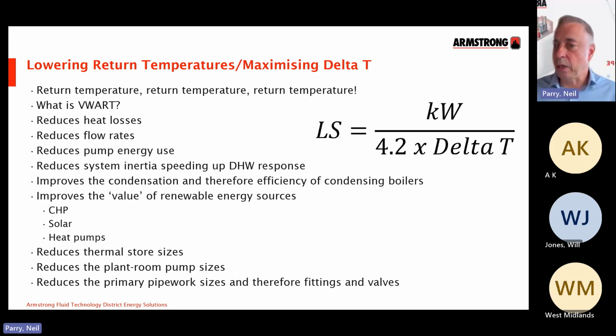We reduce heat losses from the network because you've effectively got one hot pipe and one much cooler pipe, so you've reduced those losses. We reduce the flow rate that's required, so your pump energy is less, the size of your pump is less. You've reduced system inertia, and this is a very interesting aspect of district energy or district heating systems and district cooling systems, in that the greater the size of the pipe, the greater the inertia in the system.